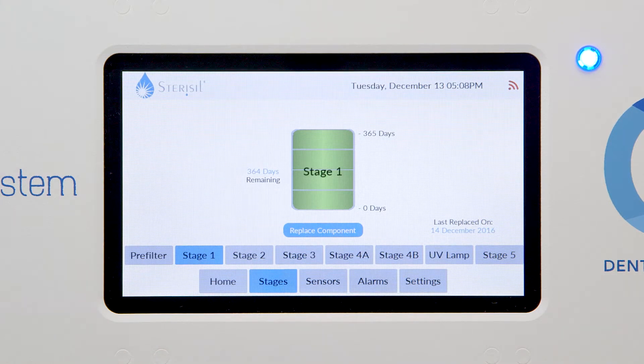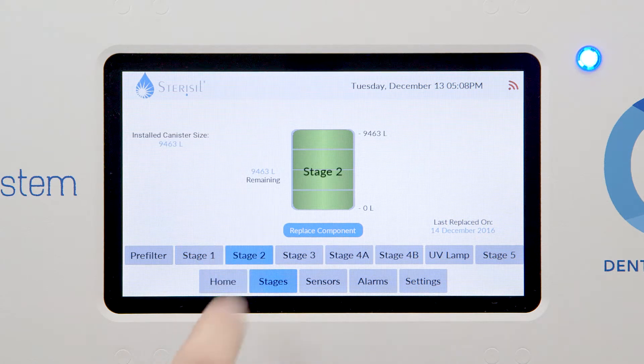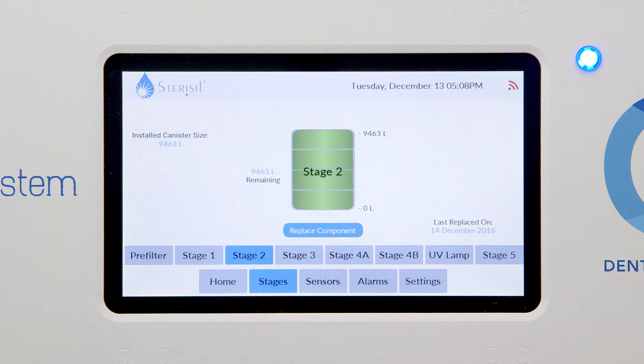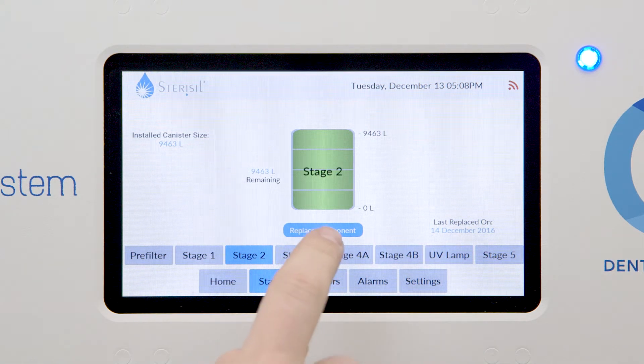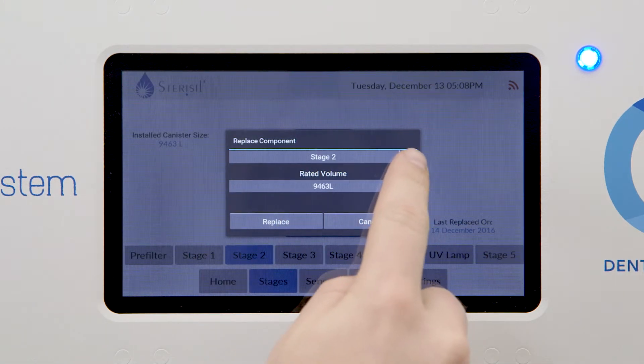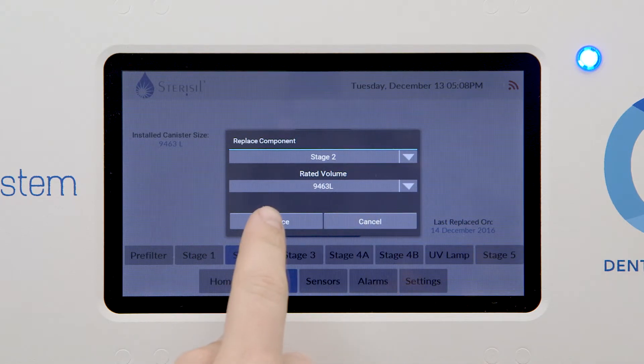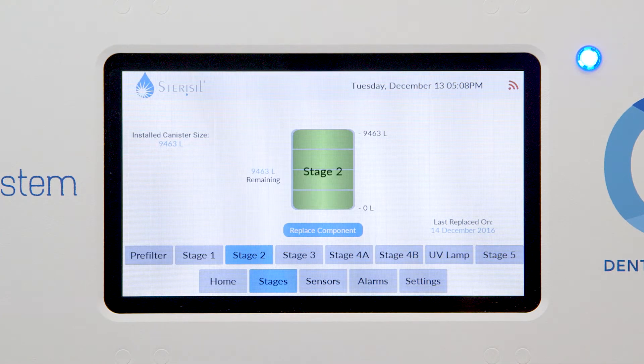Stage two's lifespan is based on liters processed and is effective up to 9,463 liters. If the counter is not reading 9,463 liters, you'll select replace component, choose stage two from the drop down menu, and touch replace.